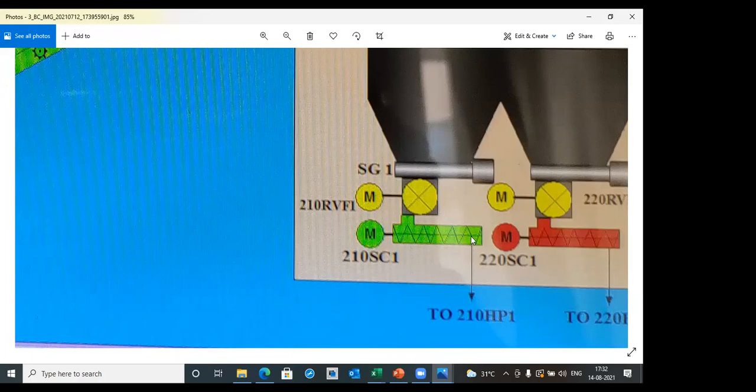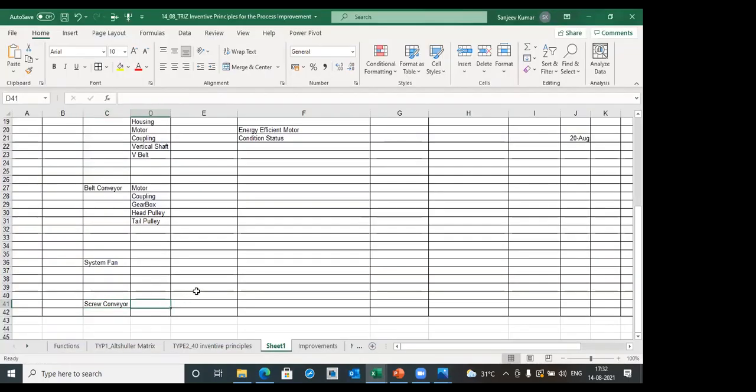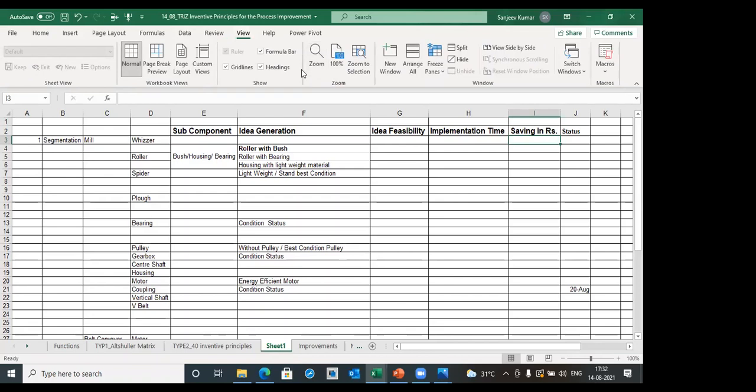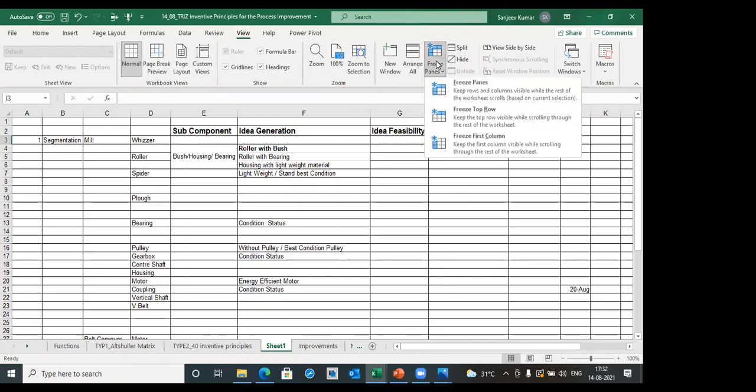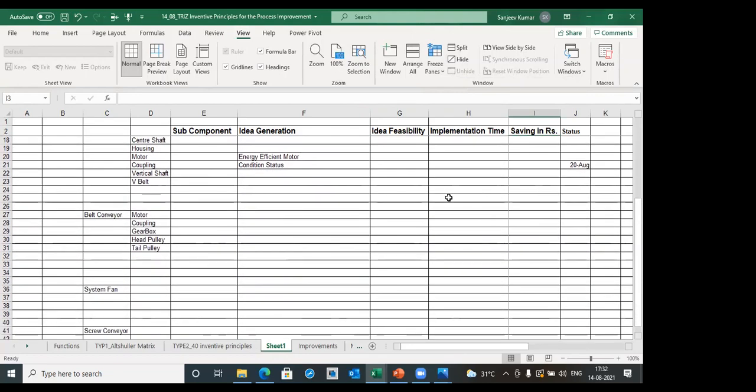the continuous feeding of product, and this screw conveyor is ranging from 5.5 to 7.5 kilowatt capacity power. So the power rating is from 5.5 to 7.5 kilowatt. This 7.5 kilowatt motor runs throughout the entire running of the mill. We are only able to stop the rotary feeder, which feeds the screw conveyor.